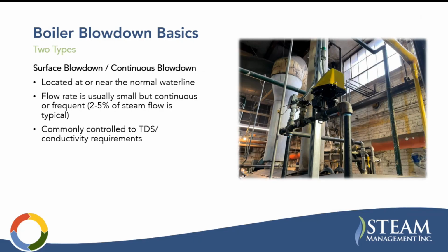There's two main types of blowdown, surface blowdown or continuous blowdown. These are the same type, so this is just one type. They're called both. This is located at or near the normal water line. Most of the dissolved solids in the boiler are from about 6 to 8 inches from the top of the water line, and so you'll locate the surface blowdown line in that area. It's basically based on the circulation pattern of the boiler where it's located. You want to put that position in a location to ensure the most concentrated water is rejected, and you want to avoid rejecting incoming feed water or chemical feed.